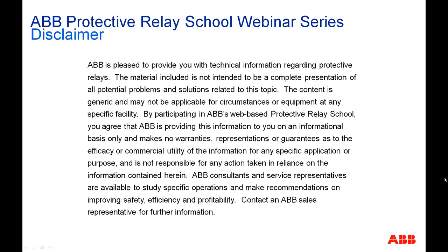There's one question: would you provide highlights of the line distance protection and compare it with the line differential? Well, during our webinar, we have been talking about the advantages and disadvantages of the line differential protection scheme as compared to line distance protection. Because of the inherent advantages of differential protection schemes, we get a highly dependable as well as selective protection with line differential protection.